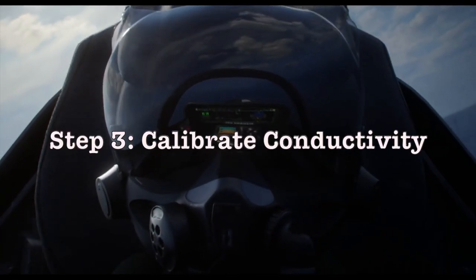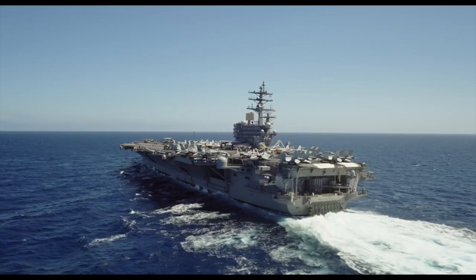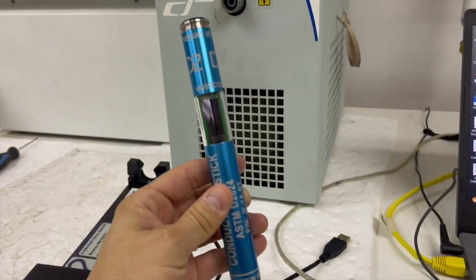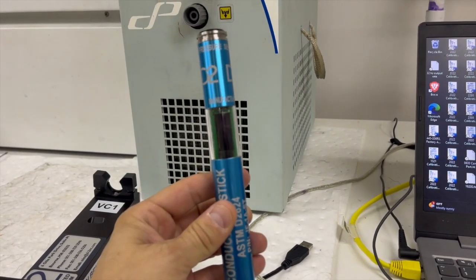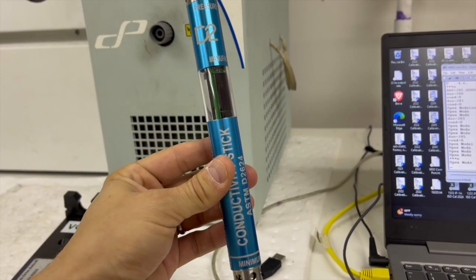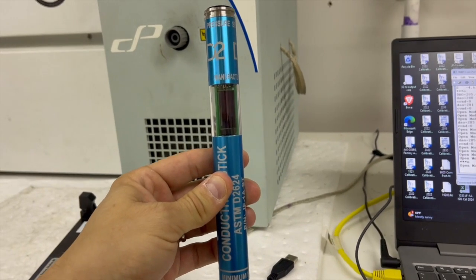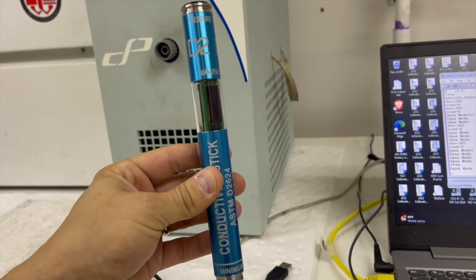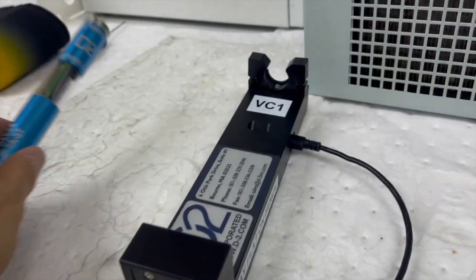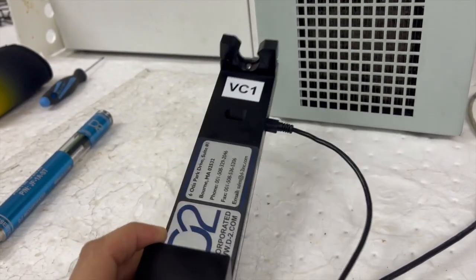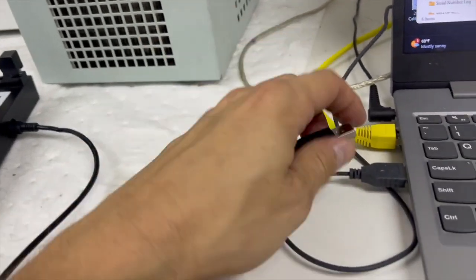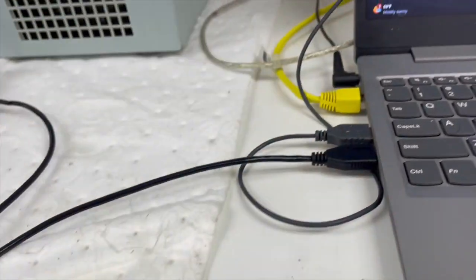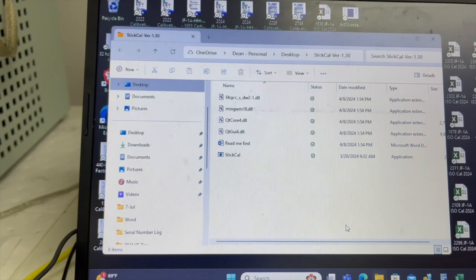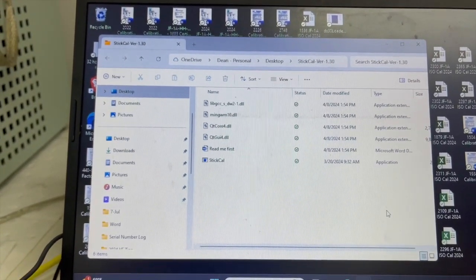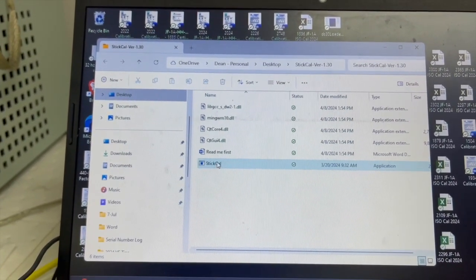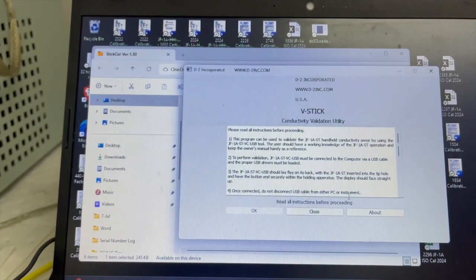The next step is to calibrate and verify conductivity. So the first thing we do is we're going to calibrate and verify that this stick works in the field. Okay, so then we know that this stick is calibrated and verified. First thing we do is, with this version, you plug the USB cord into a normal USB port on your computer, and with this will come software. That software includes a program called StickCal. You open up StickCal.